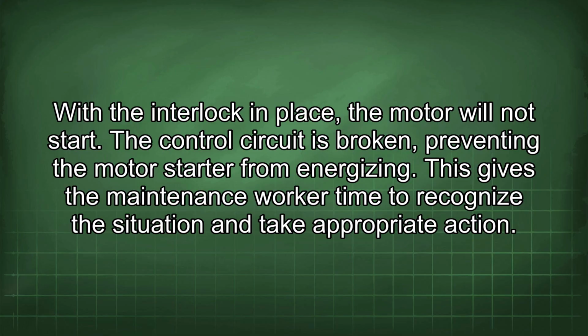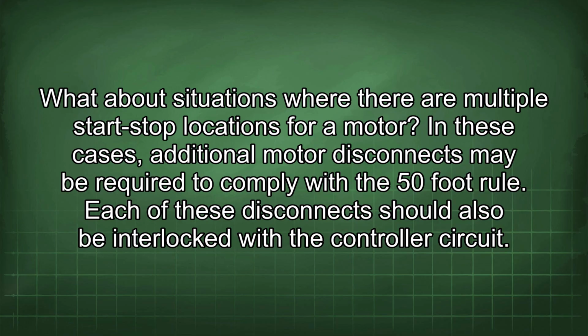This gives the maintenance worker time to recognize the situation and take appropriate action. What about situations where there are multiple start-stop locations for a motor? In these cases, additional motor disconnects may be required to comply with the 50-foot rule. Each of these disconnects should also be interlocked with the controller circuit.